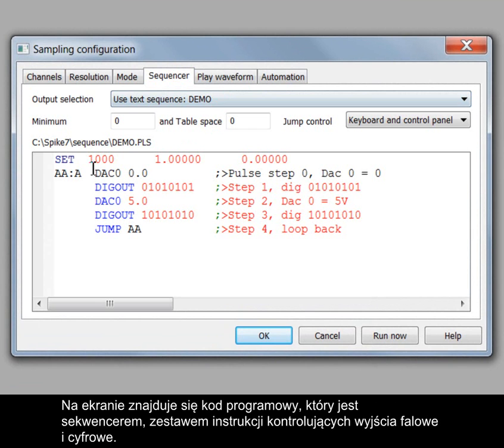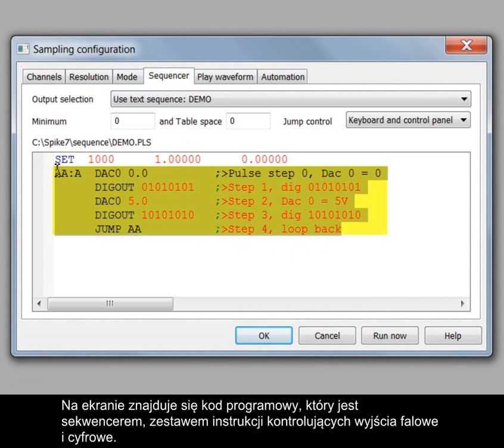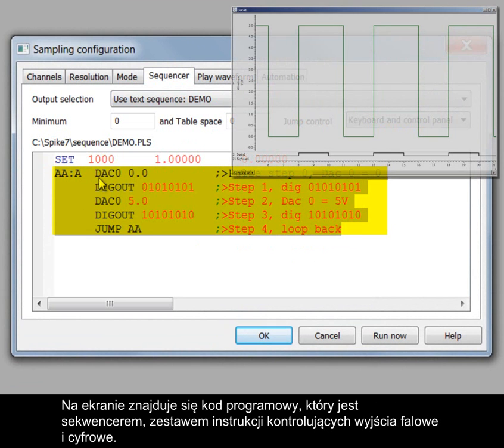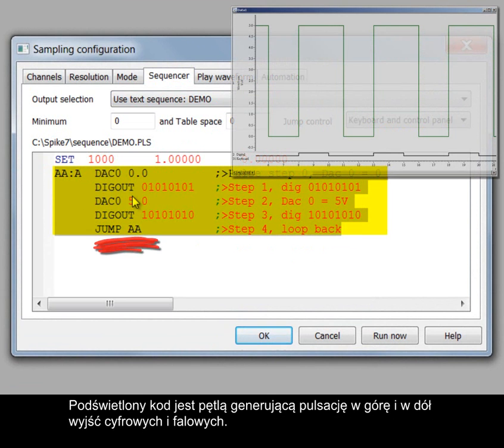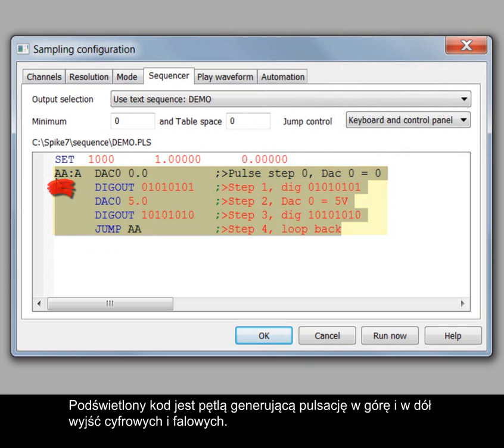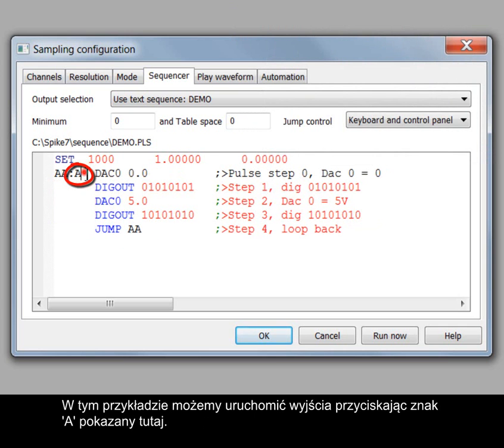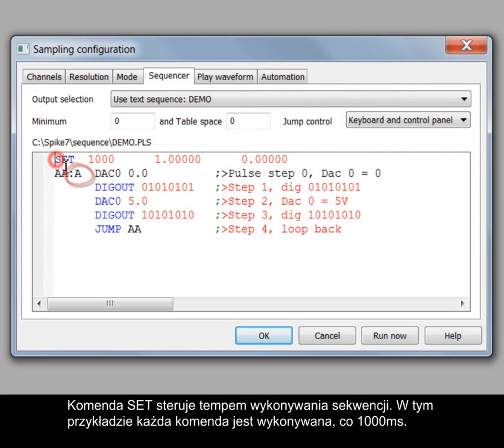On the screen is the underlying software code that is the sequencer, a set of instructions to control waveform and digital outputs. The highlighted code is a loop pulsing the digital and waveform outputs high and low. In this example we can start the outputs by pressing the character A shown here. The set command controls the execution rate of the sequence. In this example each command is performed every 1000 milliseconds.